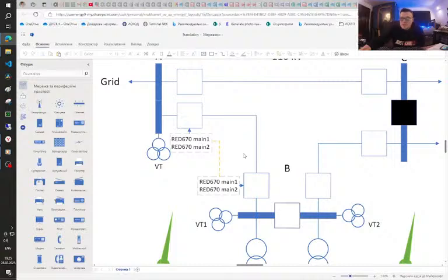differential protection was not in service. When I show you records, you will see that the channel was restored, but it was not verified by protection staff. So in this case, the line was protected only by backup functions in these IEDs. Please, do you have any questions?